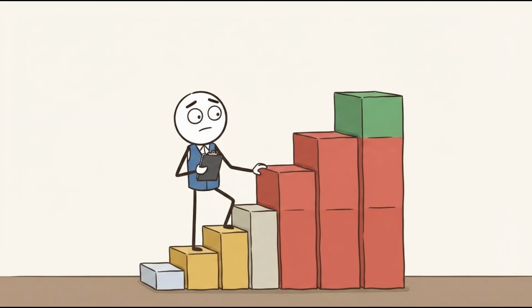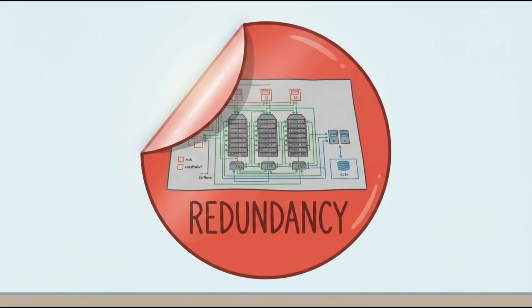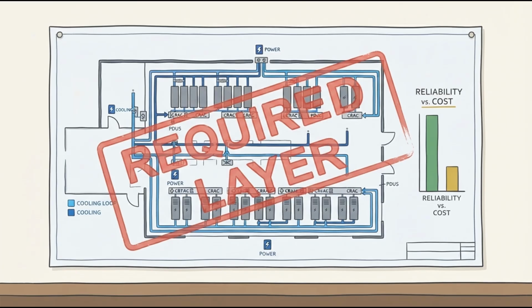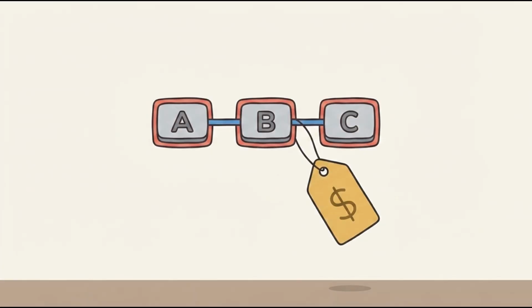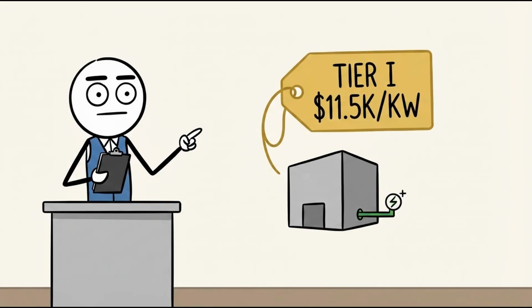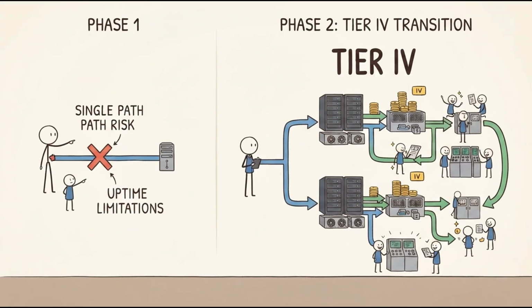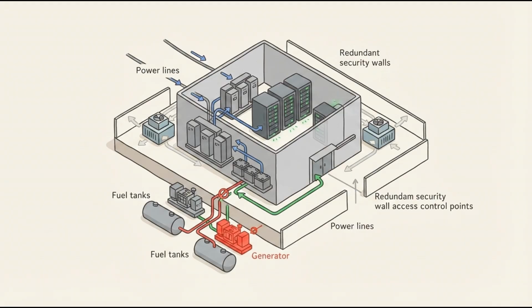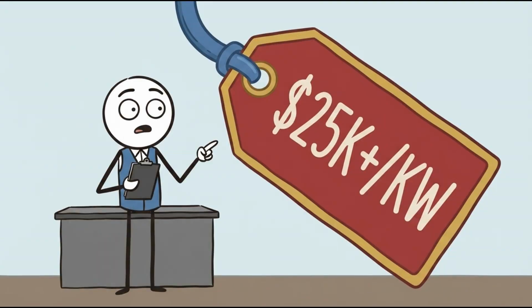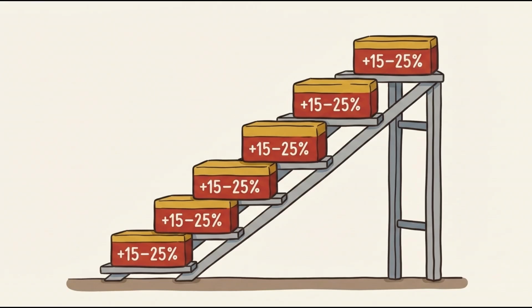Tier level compounds every one of these numbers further, because redundancy is not a marketing term in this industry. It is a design requirement with a direct dollar figure attached. A Tier 1 facility with no redundancy runs roughly $11,500 per kilowatt, while a Tier 4 facility, fully fault-tolerant and capable of surviving any single equipment failure without an outage, can push past $25,000 per kilowatt, with each step up the tier ladder adding 15 to 25% to total construction cost.